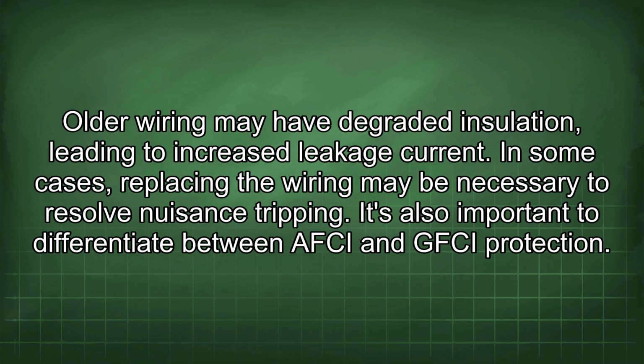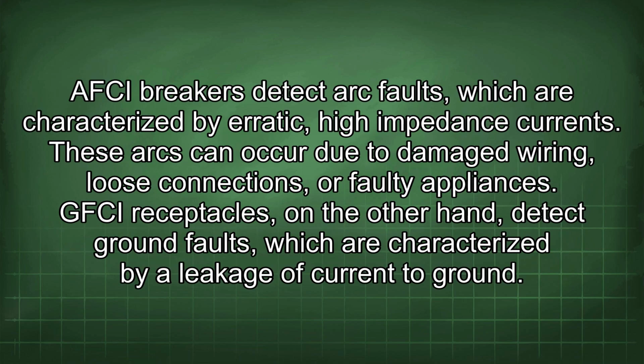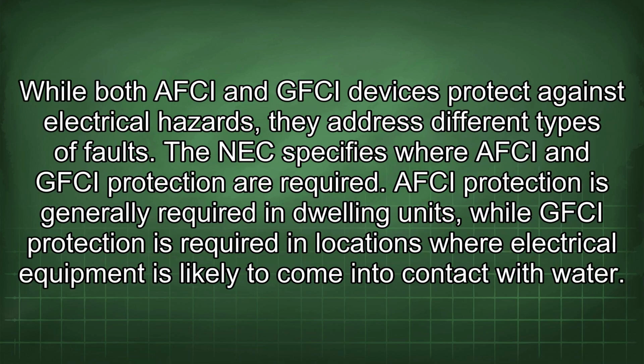It's also important to differentiate between AFCI and GFCI protection. AFCI breakers detect arc faults, which are characterized by erratic, high-impedance currents. These arcs can occur due to damaged wiring, loose connections, or faulty appliances. GFCI receptacles, on the other hand, detect ground faults, which are characterized by a leakage of current to ground. While both AFCI and GFCI devices protect against electrical hazards, they address different types of faults.